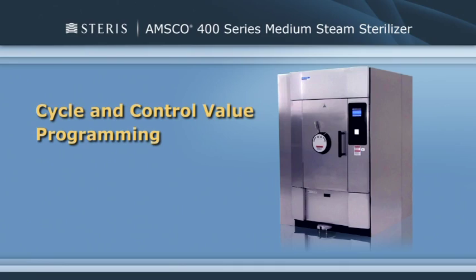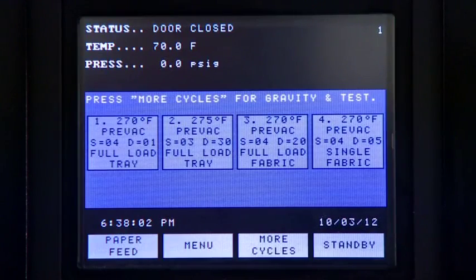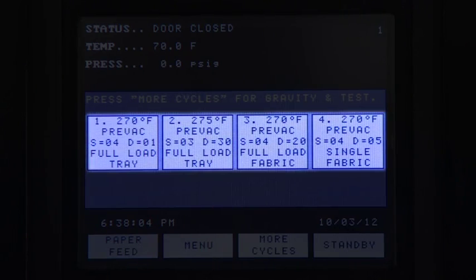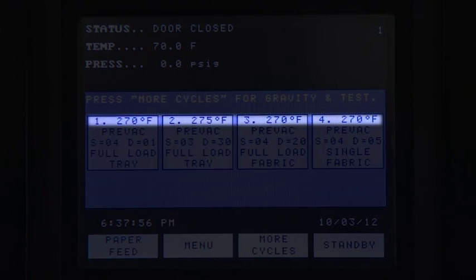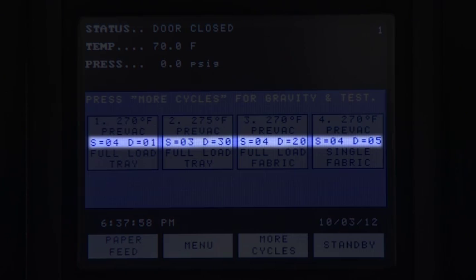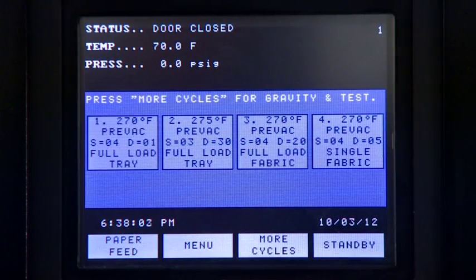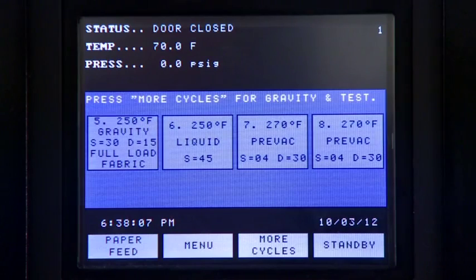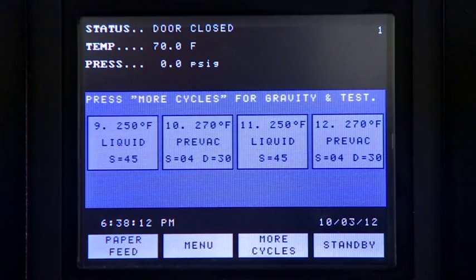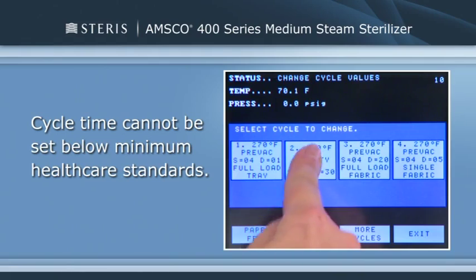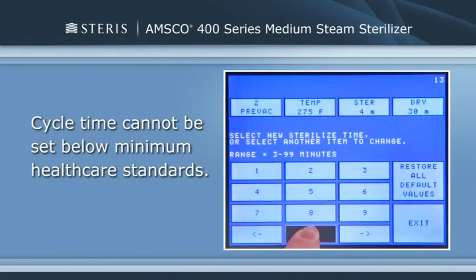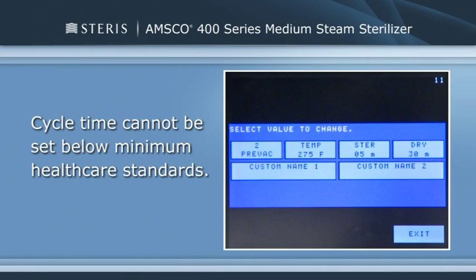As mentioned earlier, this sterilizer comes with a set of pre-programmed cycles that comply with all relevant healthcare standards. However, cycle temperatures, sterilization times, and dry times can be changed to meet specific instrument manufacturer reprocessing instructions. You can also choose which cycles are displayed on the main control panel display and change the sterilizer settings. Sterilizer time can be adjusted upward to a maximum of 99 minutes, but neither time nor temperature can be adjusted below the minimum values recommended by healthcare standards.